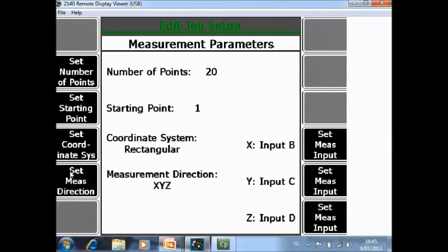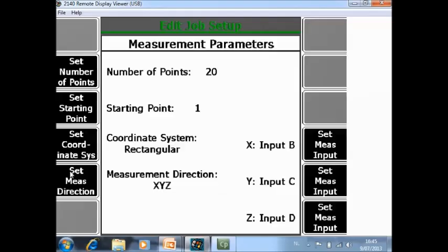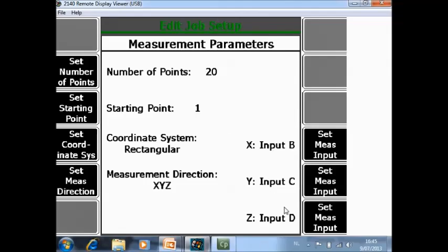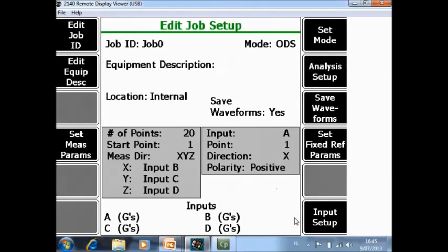Set measurement direction. Normally in a rectangular system we will work with X, Y, Z. So we accept the default X, Y, Z. Then here you can specify what your three input channels are. I will use in this application a triax sensor and my X direction is channel B, Y is channel C and Z is channel D as a default setting.